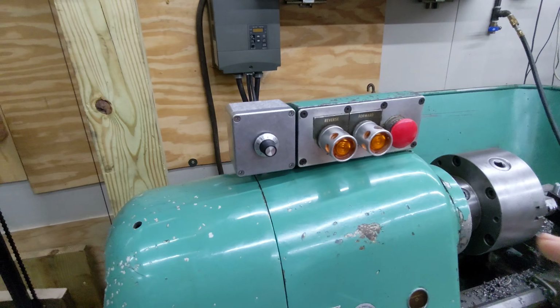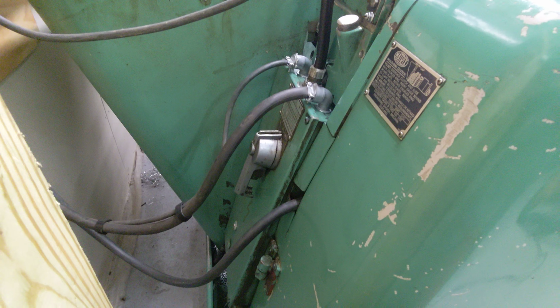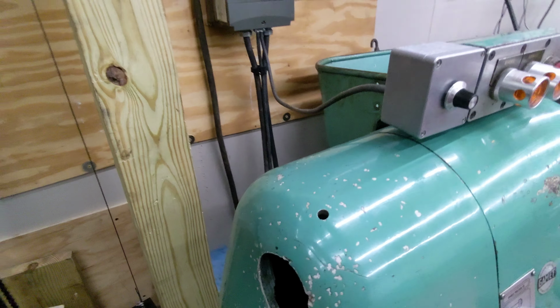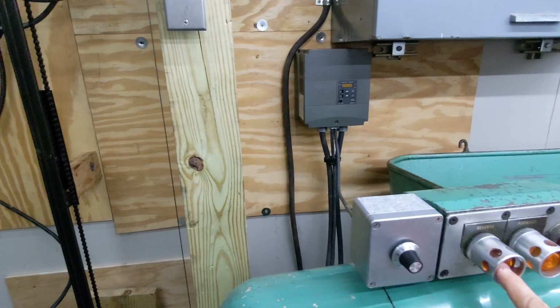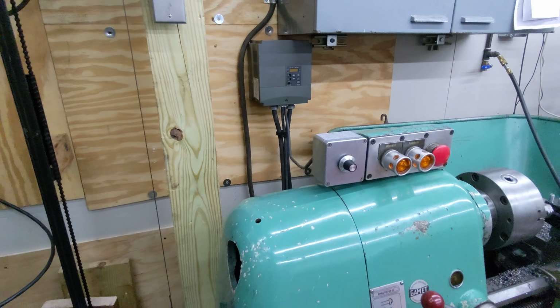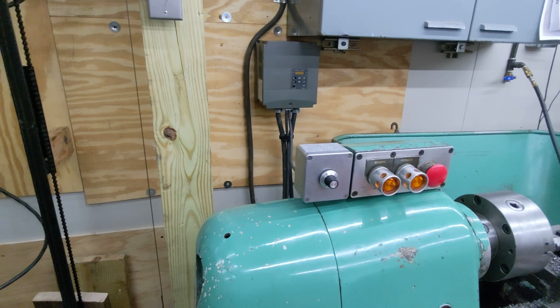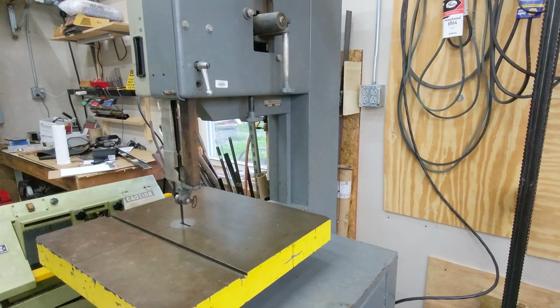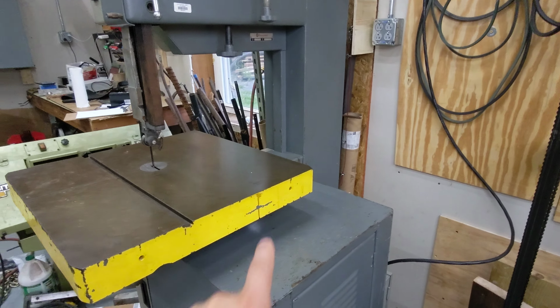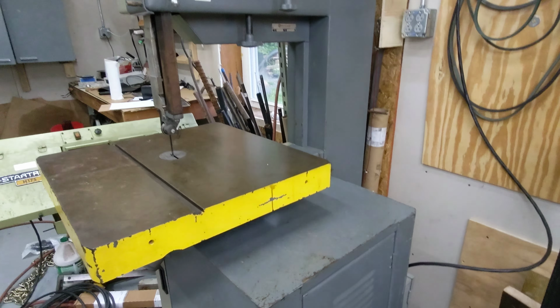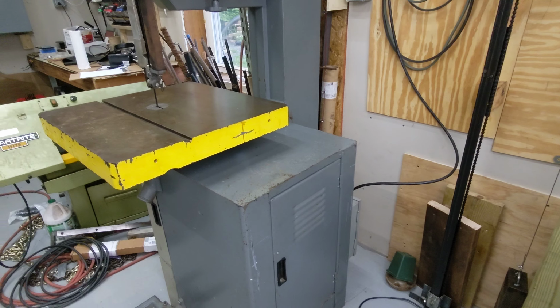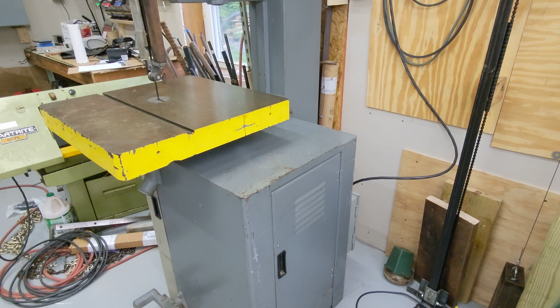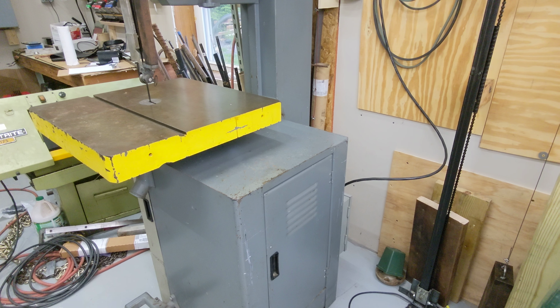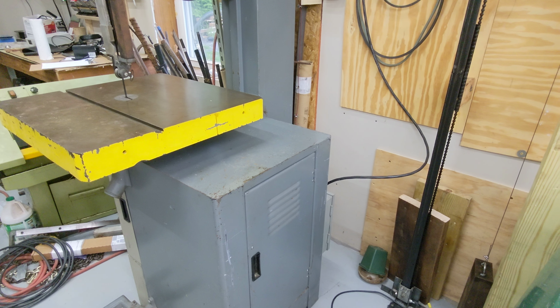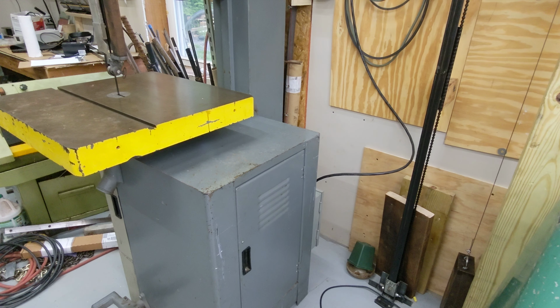I do something similar here with the electronics cabinet in the back of this lathe, which has contactors for starting the motor in forward and reverse. I'm using those to control low voltage inputs to the VFD. So these original push buttons actually still work, and they just open and close the different contacts on the low voltage side of the VFD. So similar setup between the two machines. The difference in this one is that it was a motor starter that I needed to do a little more rewiring on and bypass the heaters, and make a little more change to how the coil for the contactor was self-latching with the contactor, to ensure that the high voltage does not get sent to the VFD.